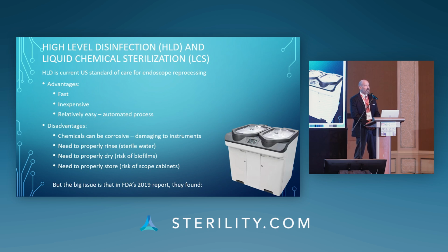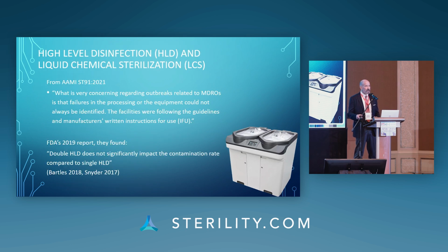Finally, scopes that have been going through high-level disinfection need to be stored properly. In the United States, the standard is putting them into a scope cabinet. Frequently, the scope cabinets themselves are not well maintained, and they can become their own source of recontamination of the scopes. But again, the big issue, going back to the FDA's 2019 report, is that high-level disinfection is not always successful in eliminating these very dangerous organisms, and multiple cycles of high-level disinfection are not successful in eliminating these organisms.